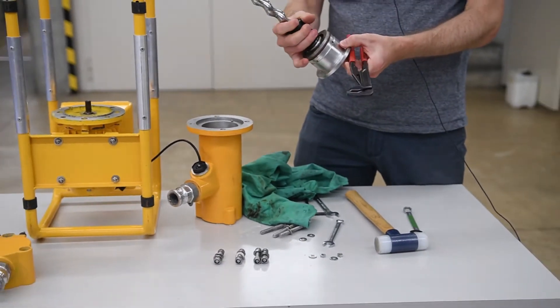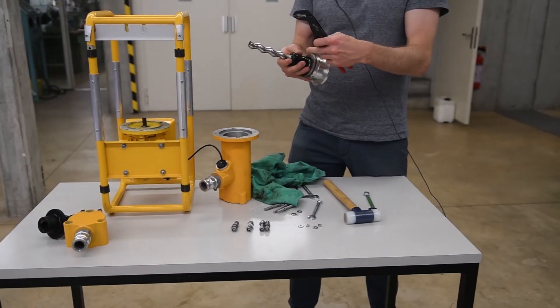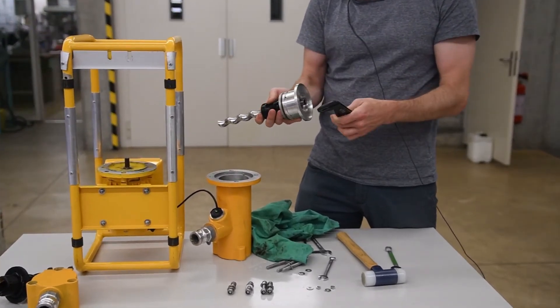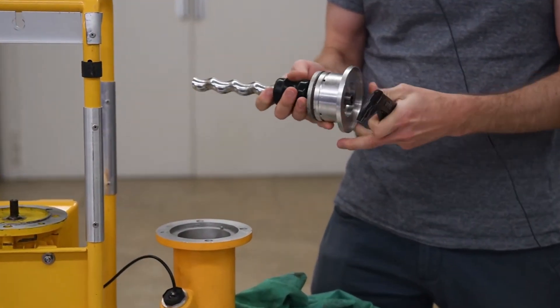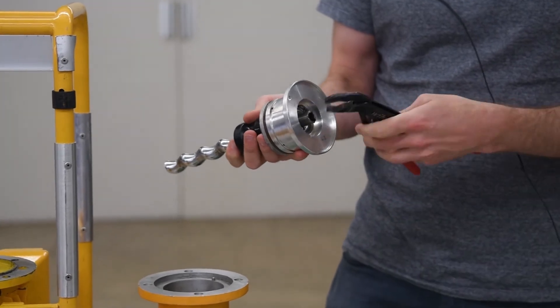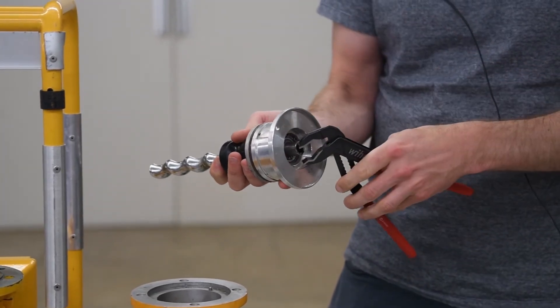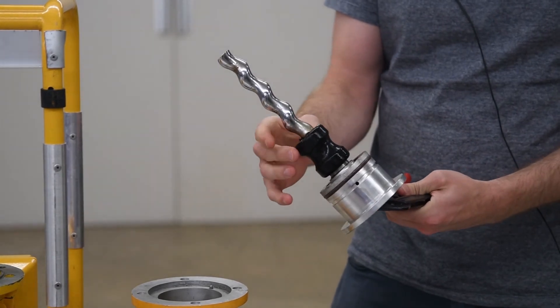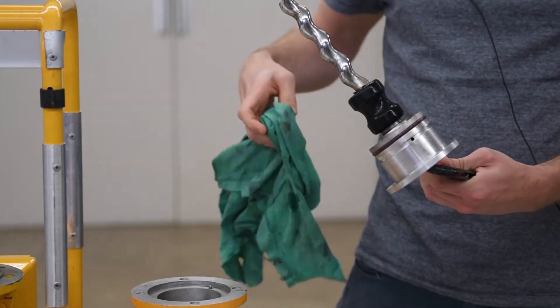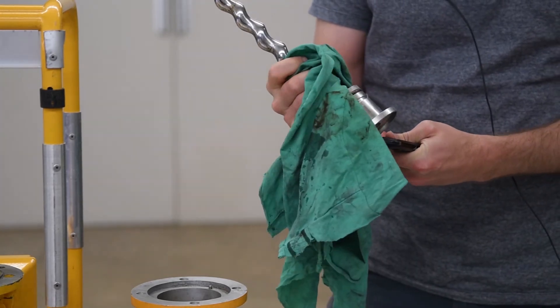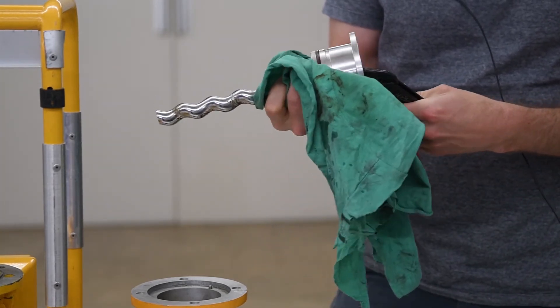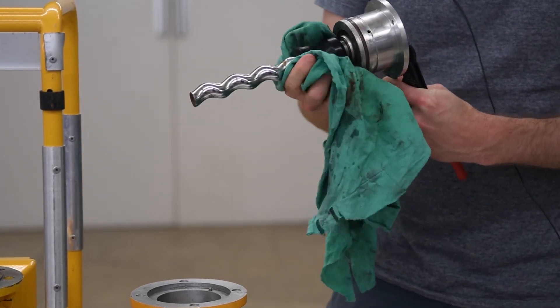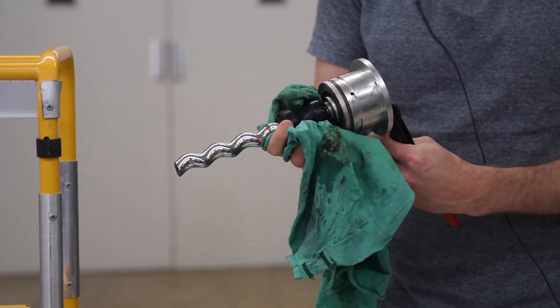We can remove the pump rotor and coupling from the insert by holding the shaft with the tool here and on the other side, because it's very slippery and wet, you can use a normal towel and then turn it to the left side.